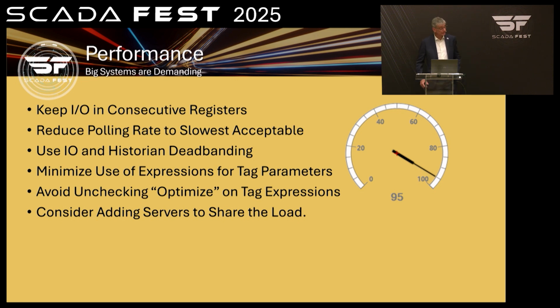So consider adding extra servers to share the load. One of the ways you do that is you split some of the drivers over one machine, others over another. One trick that you can use, though you don't see it very often, is to take one PLC and create 2 VT-SCADA drivers for it. It seems odd, but you can. You split half the tags in one driver, half the tags in the other, and then you say that driver's going to run on this machine, that driver's going to run on that machine. You've basically split the load across 2 different machines without ever having to add another PLC. And of course you have them fail over so that if one of them dies, the other one takes over the full load.